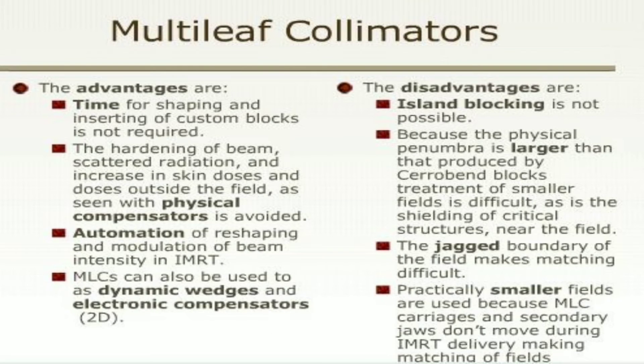Advantages of multi-leaf collimators include: time for shaping and inserting custom blocks is not required; hardening of beam scattered radiation and increase in skin dose and dose outside the field as seen with physical compensators is avoided; automation of reshaping and modulation of beam intensity in IMRT is possible. MLCs can also be used as dynamic wedges and electronic compensators.